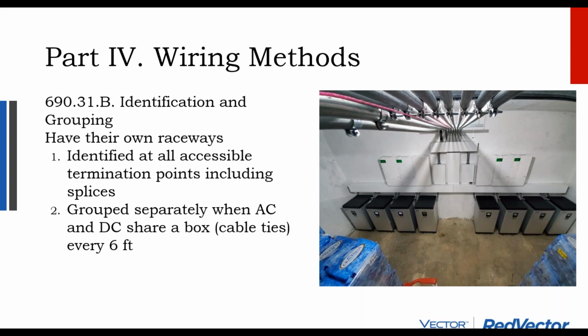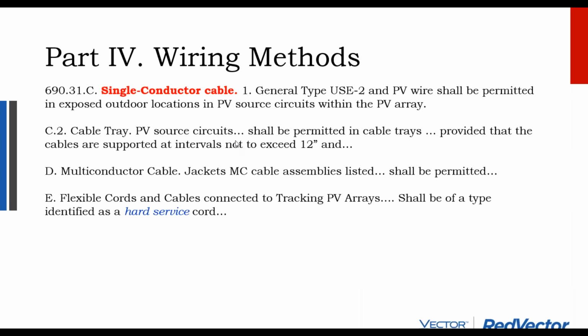In the interest of time. Can AC and DC share the same conduit or gutters or raceways? The answer is yes, but they have to be grouped separately. So generally, you'll just zip tie up the AC separate from the DC so that they're grouped separately, so you can tell which is the AC and which is the DC. Also, you generally have to keep your functions separate. So your solar circuits cannot share the same raceway and gutters as general load circuits. But you can combine the AC output of the inverter and the DC input inside the same gutter. You just have to be a little organized about it.